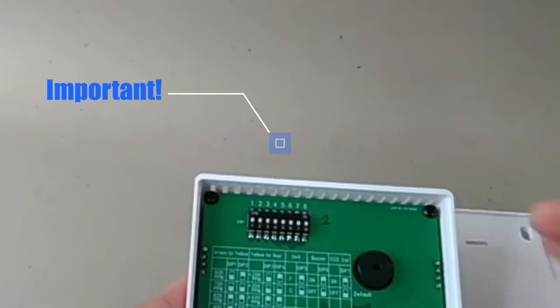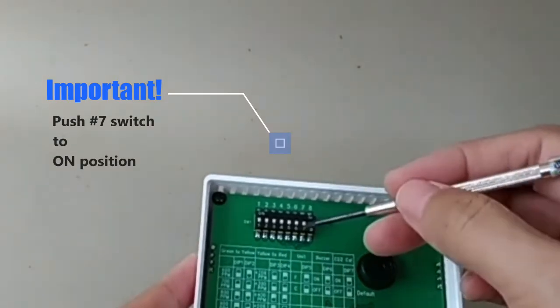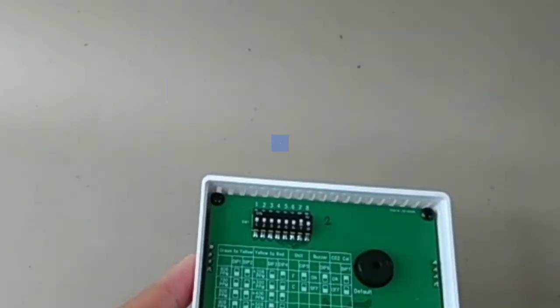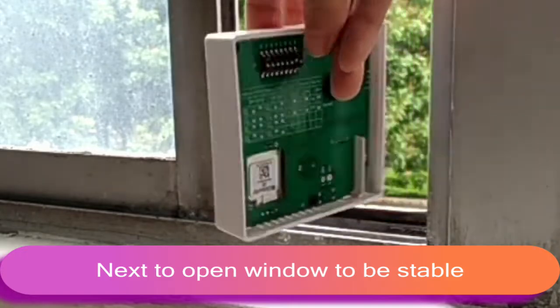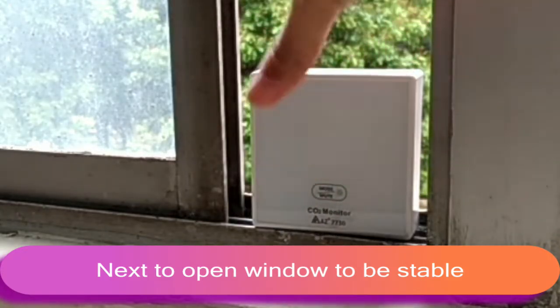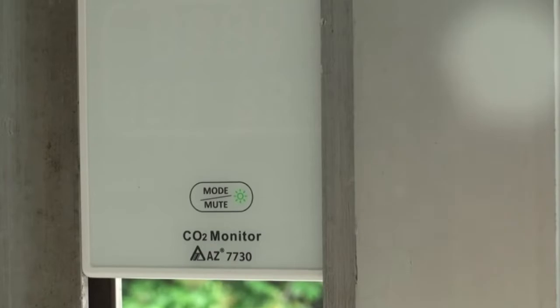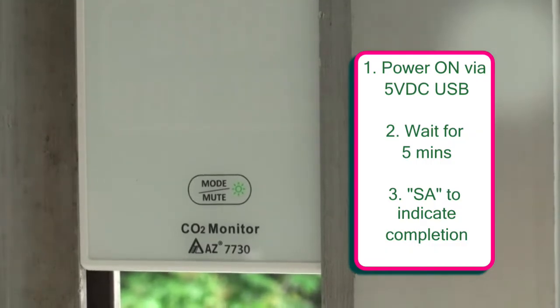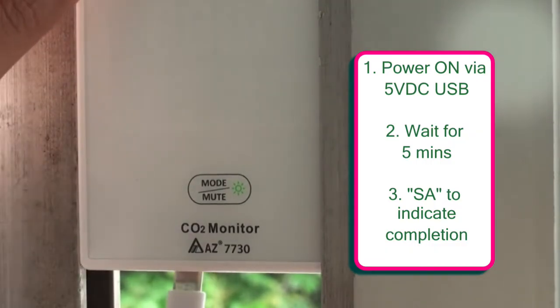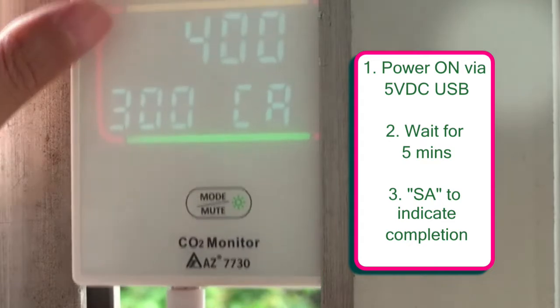Use a flat screwdriver to push the number 7 dip switch to the on position. Leave the monitor close to an open window for 20 minutes. Now power up the monitor via a 5-volt USB Type-C cable. A 300 seconds countdown appears to indicate the calibration is in process.